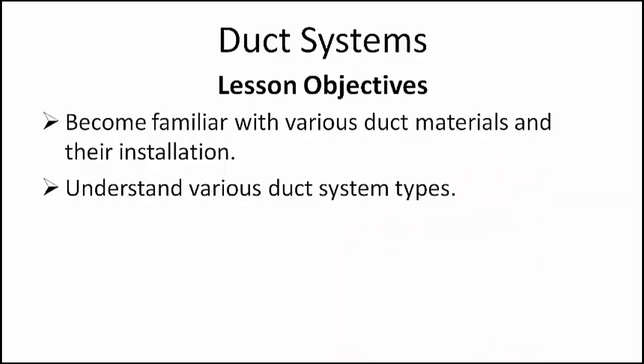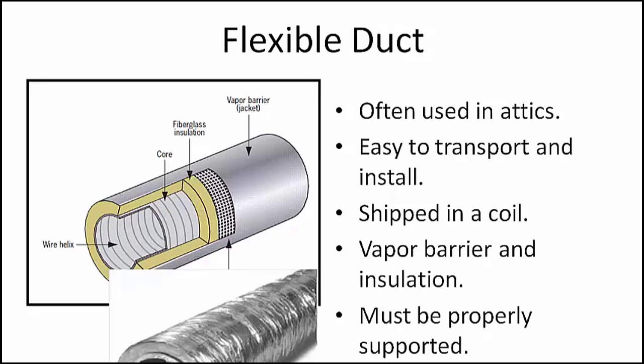We're going to become familiar with the various duct materials and their installation and understand the various duct system types. Flexible duct is used in attic installations and in other areas where there is likely to be a temperature difference greater than 15 degrees Fahrenheit between the conditioned air inside the duct and the ambient air immediately outside. Flexible or flex duct is easy to transport and install, and when selected and installed properly is an effective tool in moving conditioned air.